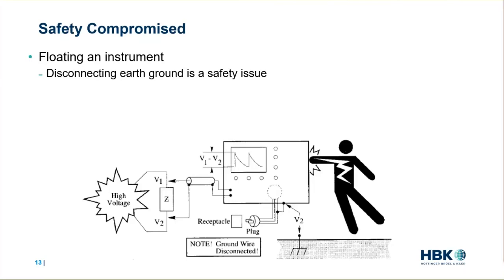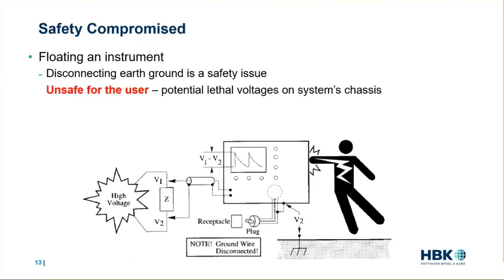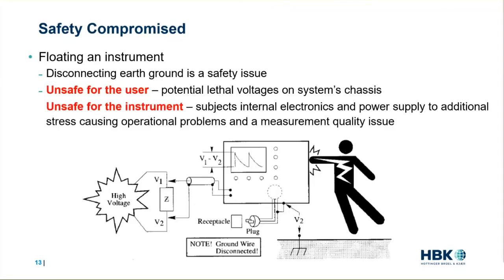Unfortunately, I still hear from time to time people floating an instrument in order to make a high voltage measurement by disconnecting the earth ground of the measuring device. Unfortunately, this creates a huge safety issue. In fact, it's unsafe for the user because you have potentially lethal voltages on the system's chassis. And it's unsafe for the instrument because it subjects the internal electronics and power supply to additional stress, causing operational problems and a measurement quality issue.